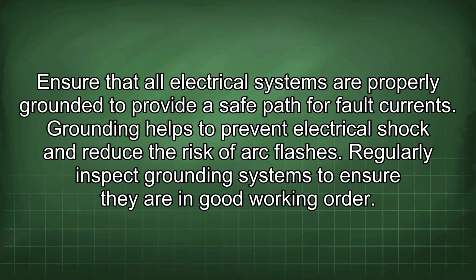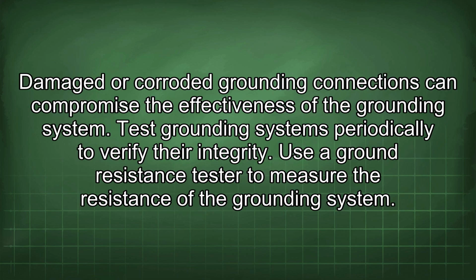Grounding helps to prevent electrical shock and reduce the risk of arc flashes. Regularly inspect grounding systems to ensure they are in good working order. Damaged or corroded grounding connections can compromise the effectiveness of the grounding system. Test grounding systems periodically to verify their integrity.